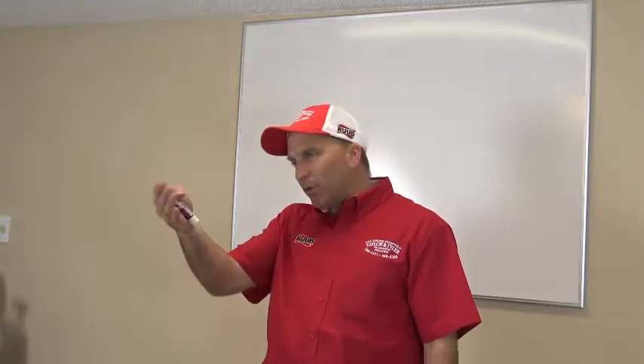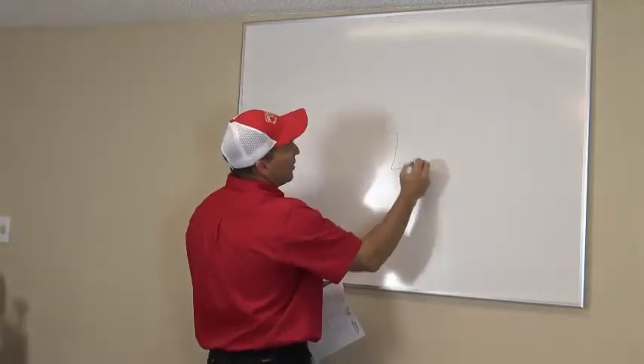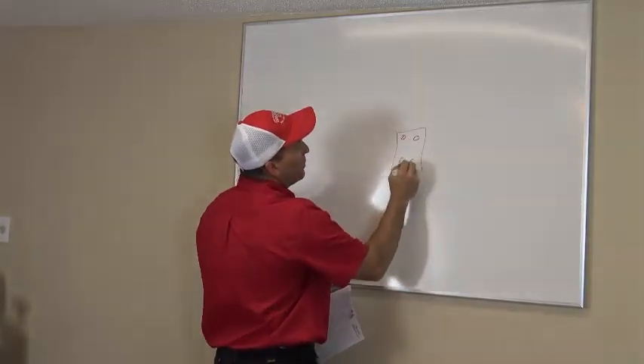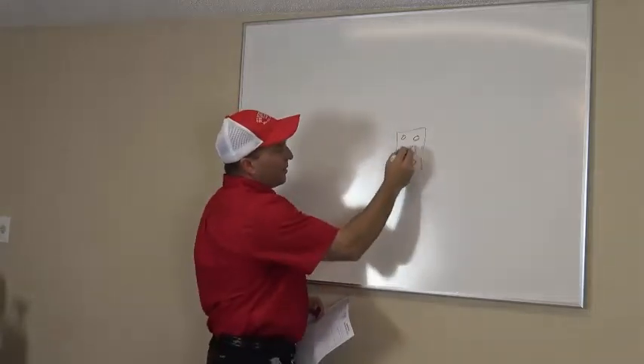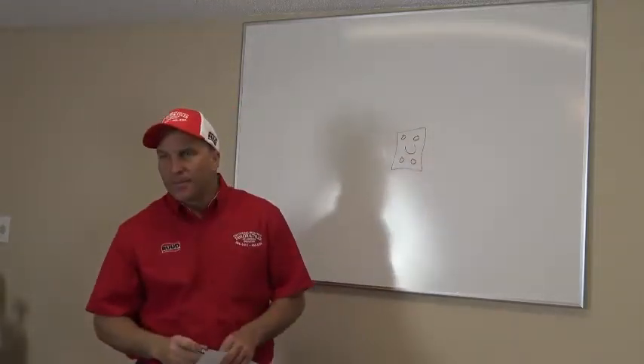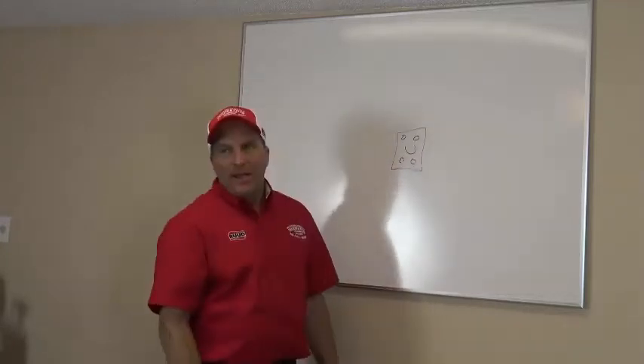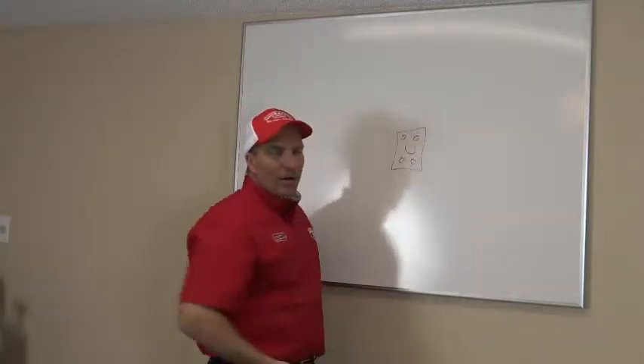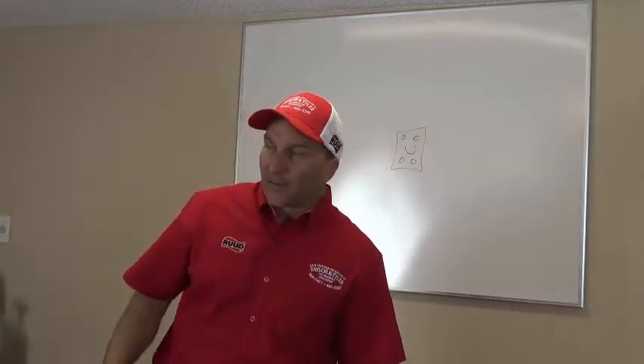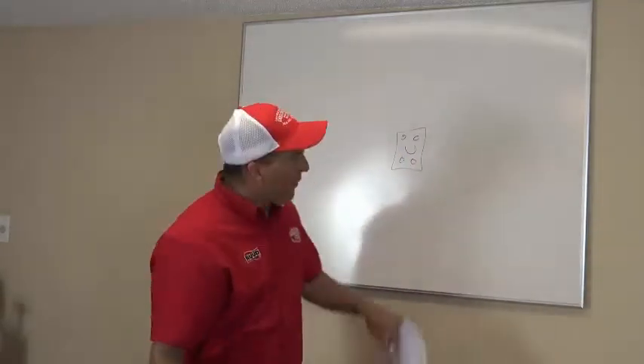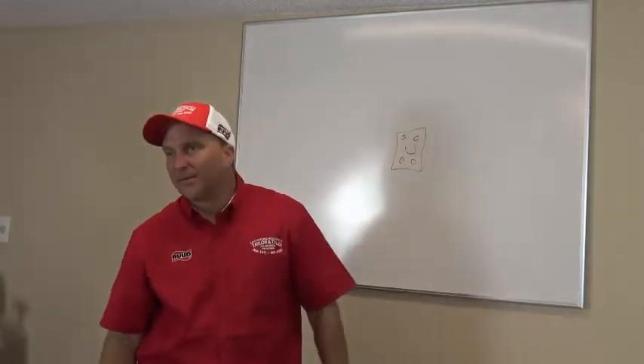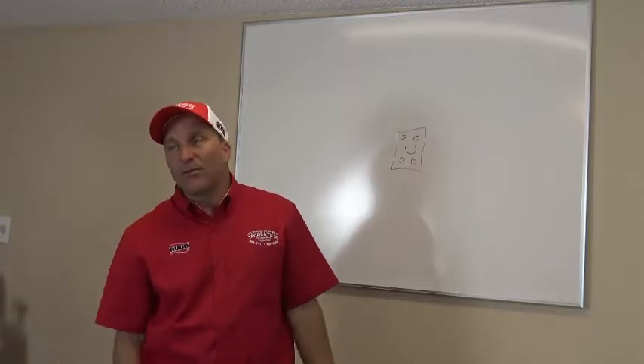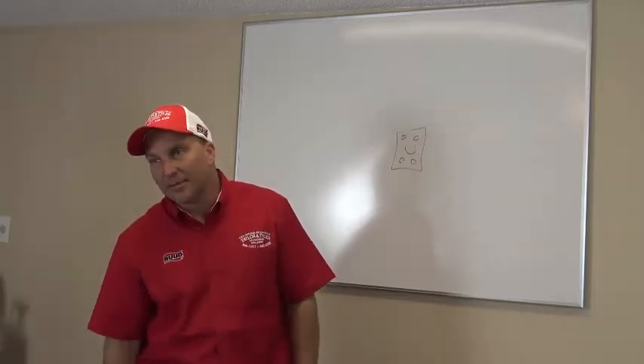Okay. Well, pull your tab off of it there, look on the inside and see if your wires are burning inside of it. Tighten everything up. Get your connections on it. If you look at your disconnect box or your pullout, guys, on your pullout, there are 4 little deals like that, right? And you got your little handle, right? If you look at this pullout, and you can literally see the screw holes right here where you can stick your screwdriver on and tighten it, it's bad. It overheated and melted that little plastic inside there. So if you see that, I'm telling you, you got burnt fuses, you got a bad disconnect, you got to replace your disconnect. Okay?